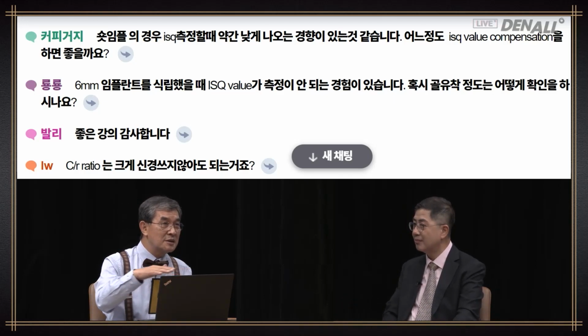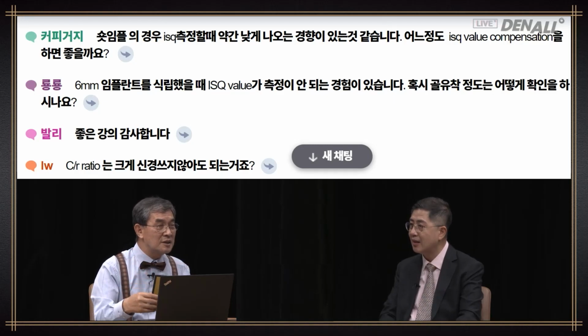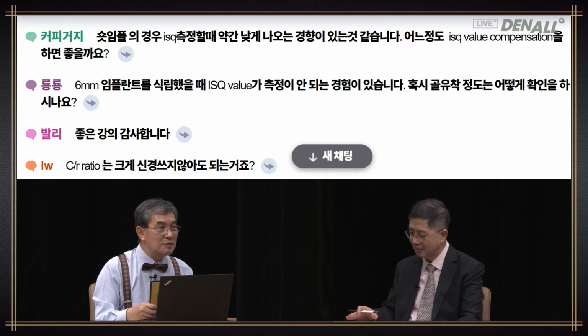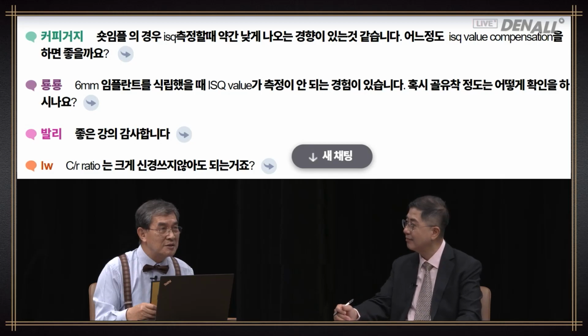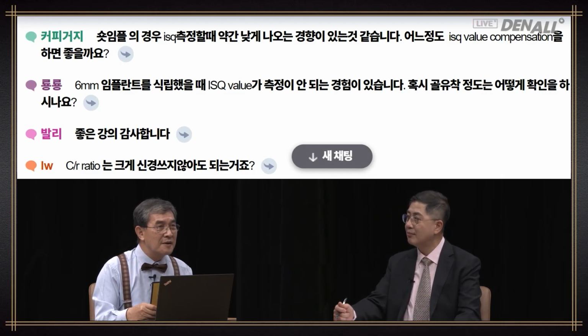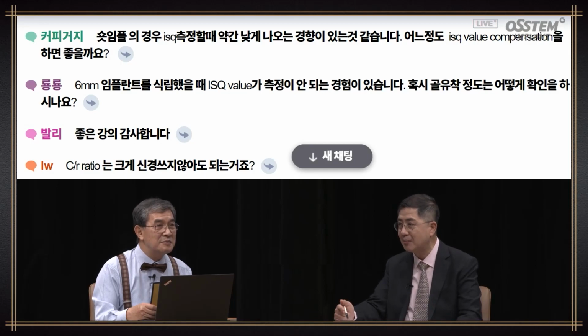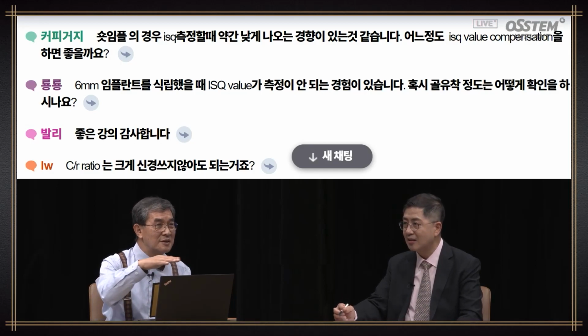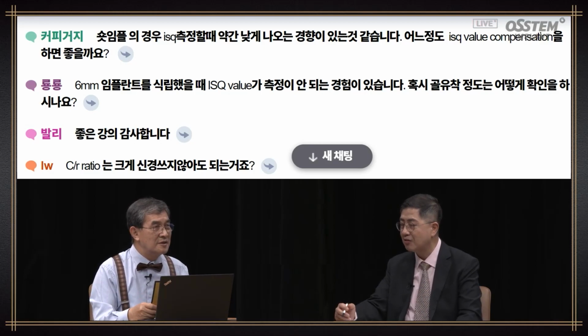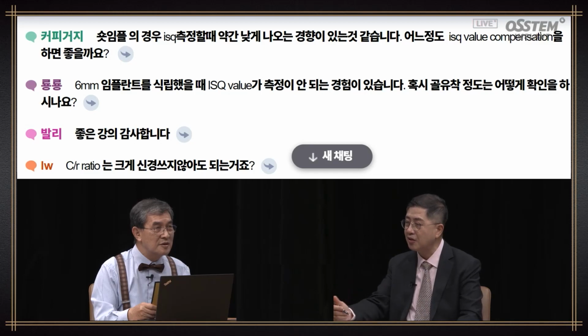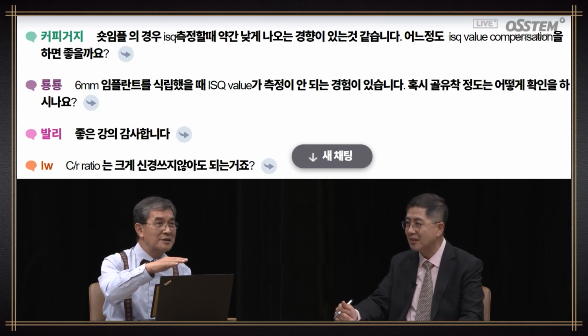Based on our clinical experience, if it's over 70, I regard it as fine, even if you use short implants. Do you frequently see over 70? In most cases, I see ISQ values of 80s rather than 70s. After 6 months, if I unscrew because of an issue, the ISQ value is over 90. In the past, the ISQ values that I saw were 70s, but now I see ISQ values in 80s and 90s.